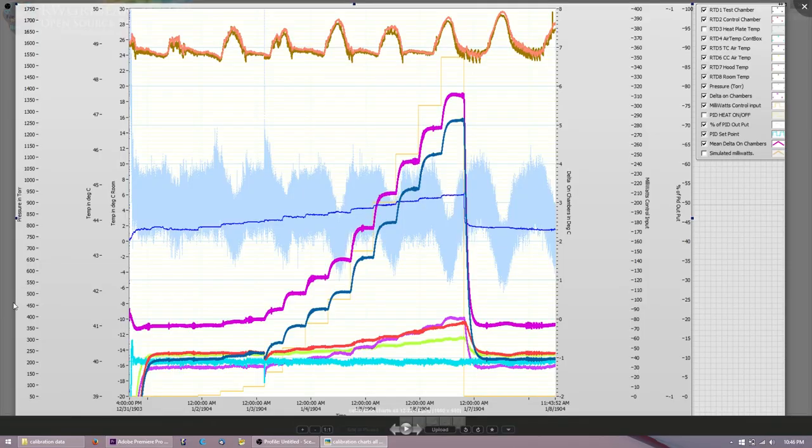So, you know, that's really, really, really good. I'm really pleased with that because of the room temperature. This room is not controlled very nicely. So, I have to do that a little bit with these heaters and try to keep it at a steady temperature. And even when the room swings really high and low, that's still close to my error tolerance. So, I just need to take note when I do everything that if my room swings more than those temperatures, my error tolerance actually moves up a little bit. And I have all those calibration curves and been doing lots of testing for weeks now to kind of understand the system, know how it works, and see what's best for it and what I need to do. So, there you go. Alright, so let's go ahead and look at the calibration data.